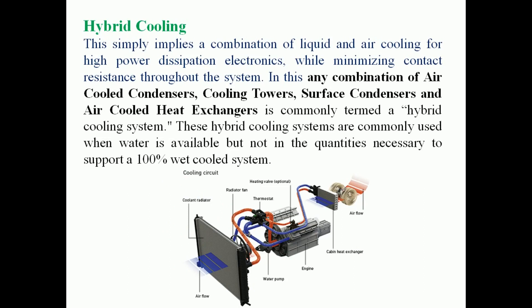Hybrid cooling uses a combination of two or more cooling systems. It combines liquid and air cooling for higher power dissipation in electronics while minimizing contact resistance throughout the system. Any combination of air-cooled condensers, cooling towers, surface condensers, and air-cooled heat exchangers is commonly termed a hybrid cooling system. These systems are commonly used when water is available but not in quantities sufficient to support a 100% wet-cooled system.